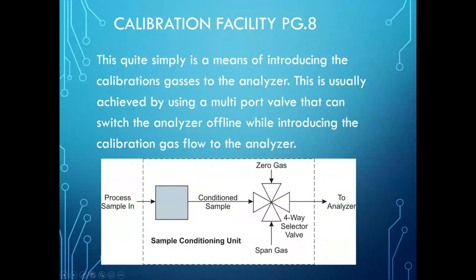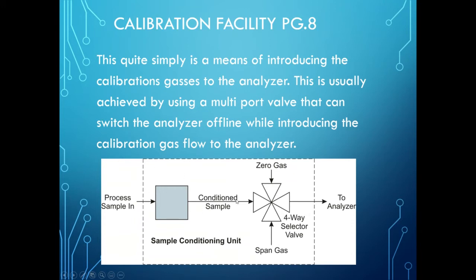One of the five functions of the sample handling system is the calibration facility — providing a means of introducing calibration gases to the analyzer. This is usually achieved using a multiport valve that can switch the analyzer offline and introduce zero gas and span gas. In normal operation the process sample goes to the analyzer; by turning the valve you can introduce zero or span gas. This is typically introduced after all the sample system hardware but before the analyzer.